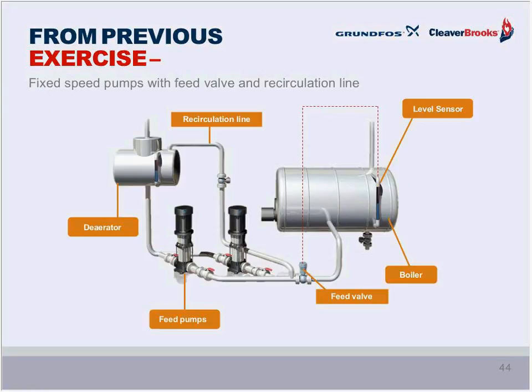Okay, so here is the last webinar, which was a month ago at the end of July. We did a selection exercise based on this fixed speed pump with a feed valve and a recirculation line, like shown here. Remember, this is continuous operation, so that requires the recirc line back to the DA tank when there's a reduced volume of water being called for.